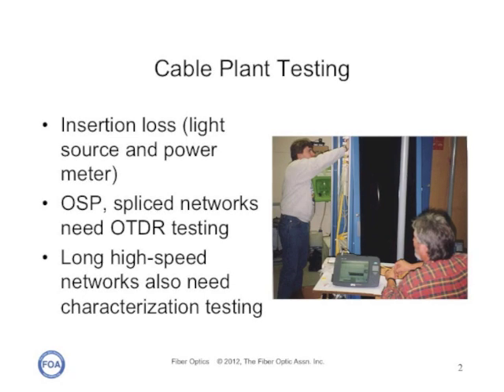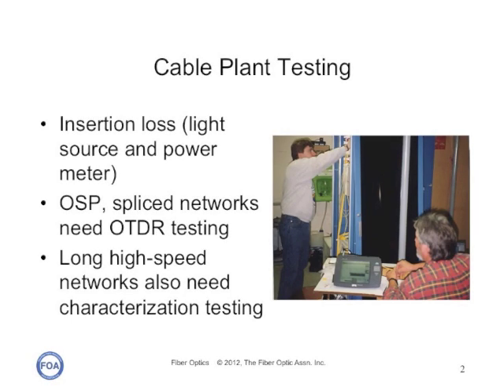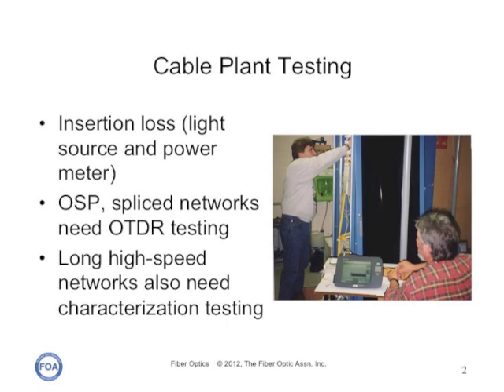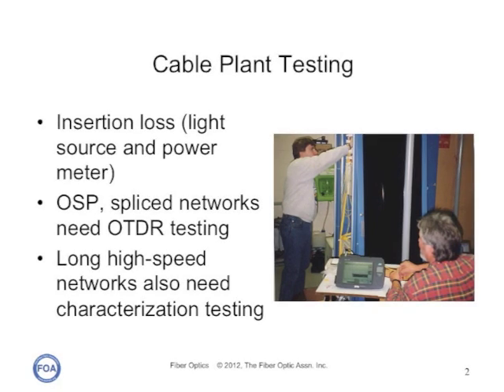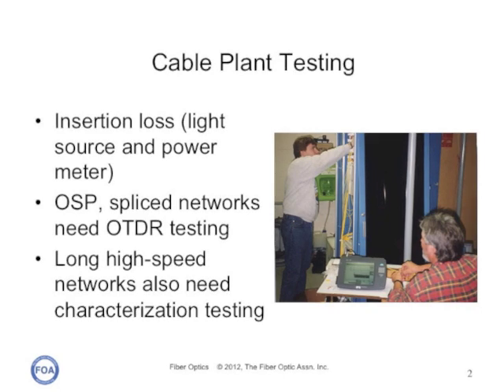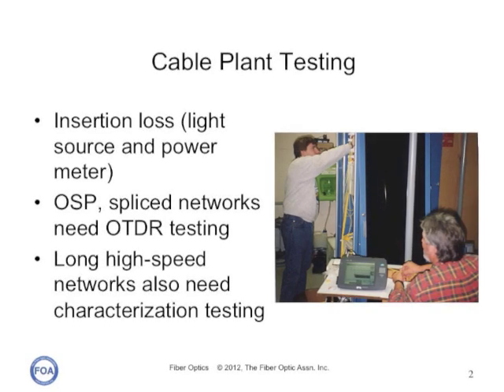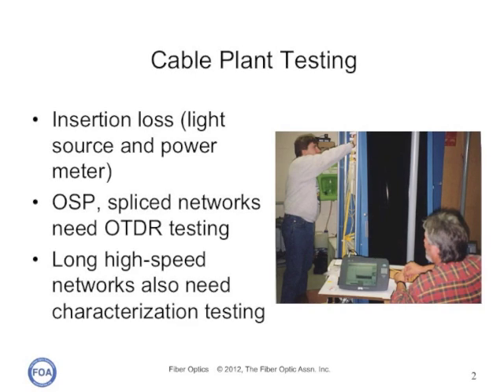Every fiber optic cable plant should be tested by a light source and power meter, called an insertion loss test, because that test mimics the way the cable plant will be used by transmission systems and provides the most reliable test data for ensuring the cable plant will work properly. Outside plant and splice networks will also get OTDR testing, because that verifies the quality of the installation and the performance of each individual splice. OTDR testing can also provide data on reflectance and optical return loss, which is also important for high bit rate systems.